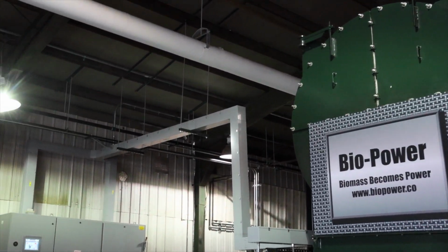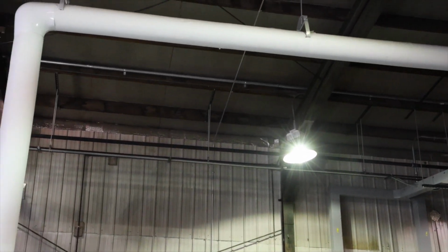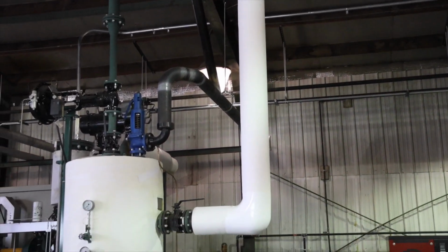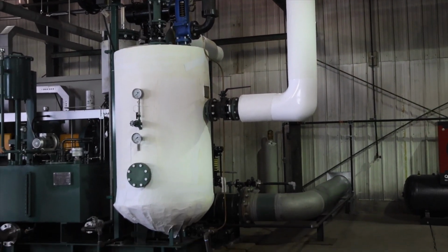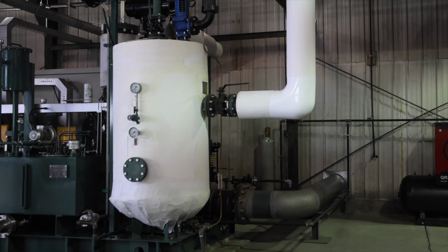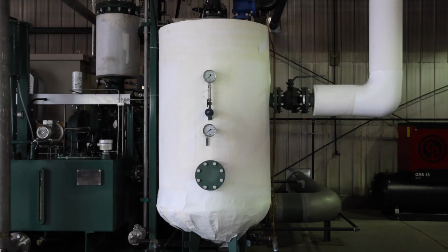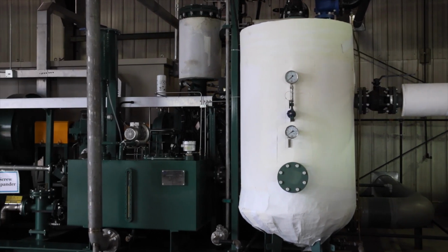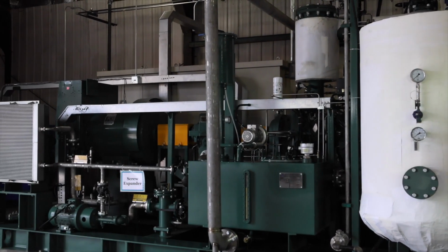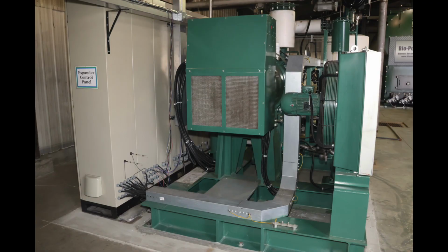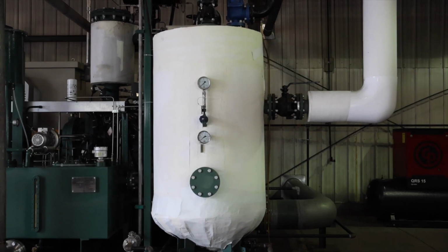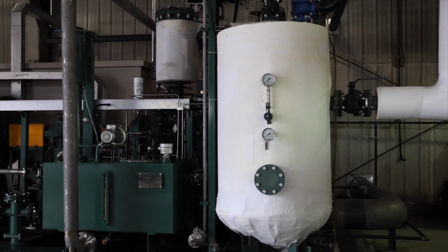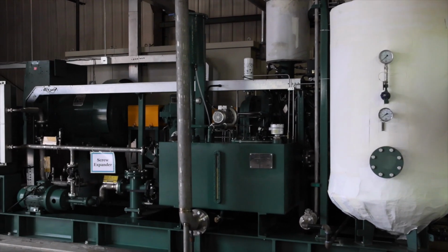From the boiler, the steam is transported to the screw expander skid to generate power. The steam enters the buffer tank and is fed into the screw expander through several automatically controlled modulating valves. The modulating valves control the feed rate of steam into the expander, thus controlling the output power produced. The screw expander skid is equipped with an oil lube package used to lubricate all moving parts. The oil lubrication system has an onboard cooling system to maintain a safe and effective oil temperature. The screw expander skid is equipped with all necessary monitoring and control equipment for safe and reliable operation.